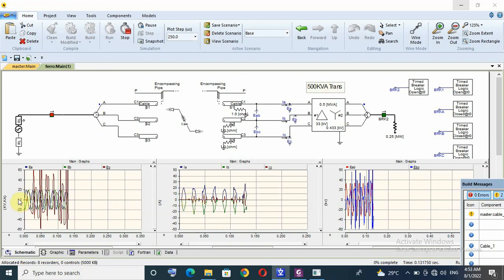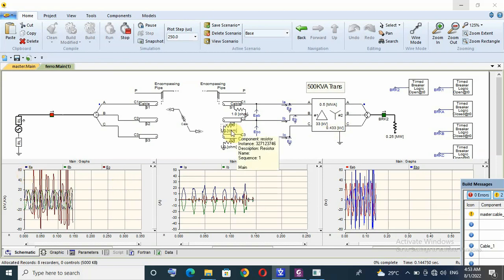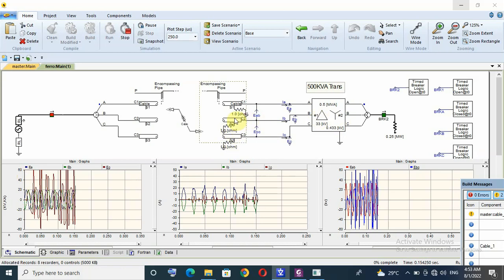Here, the overvoltage of ferro resonance phenomena is line to earth voltage above 60 kV. So, our configuration or our system is at risk from ferro resonance. And this is danger for transformer and for both transformer and cables.